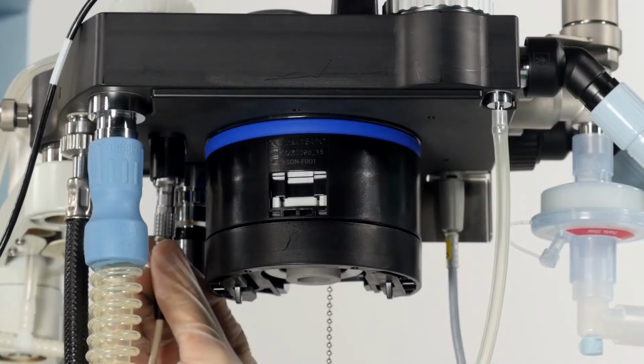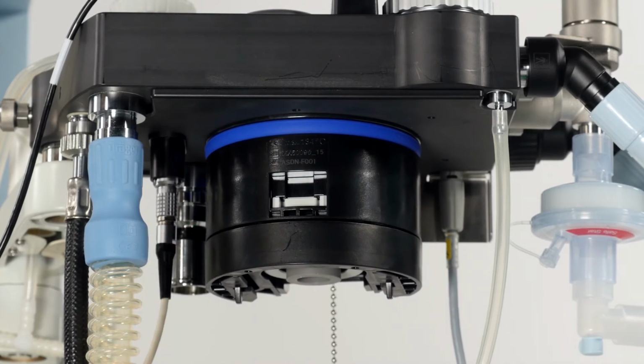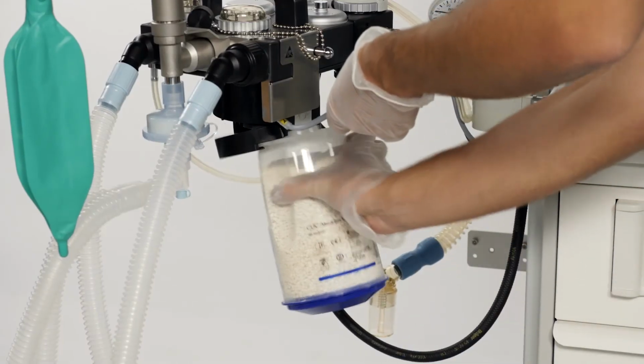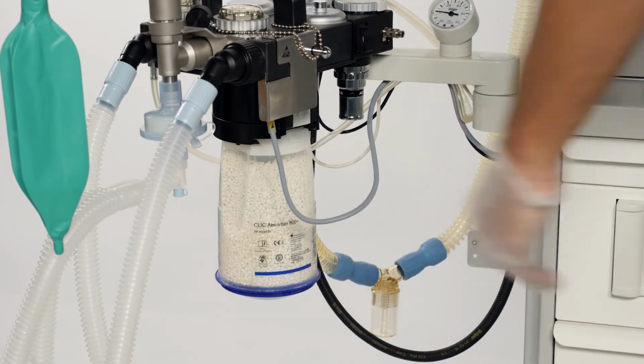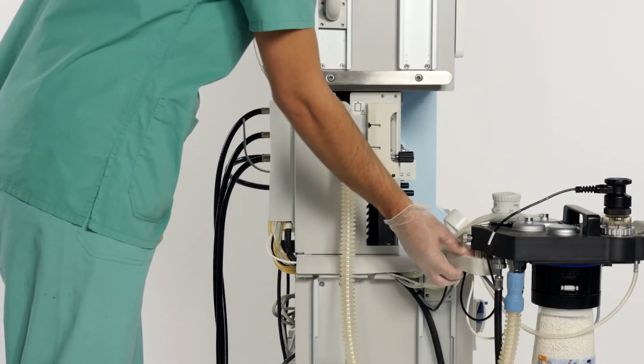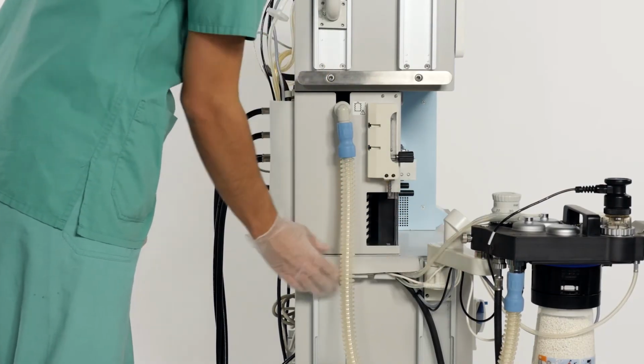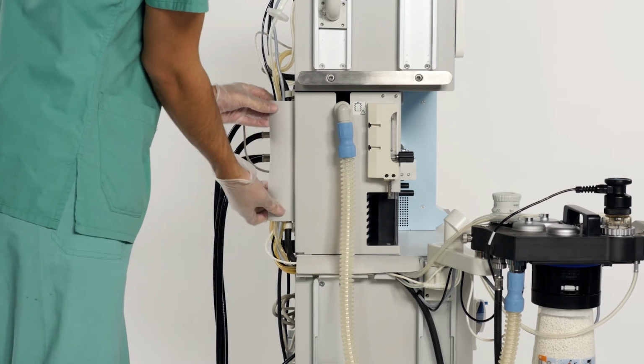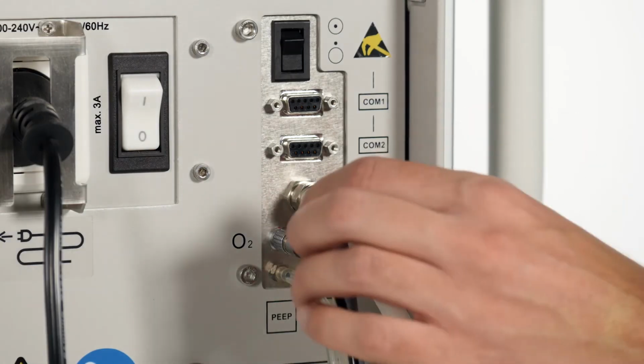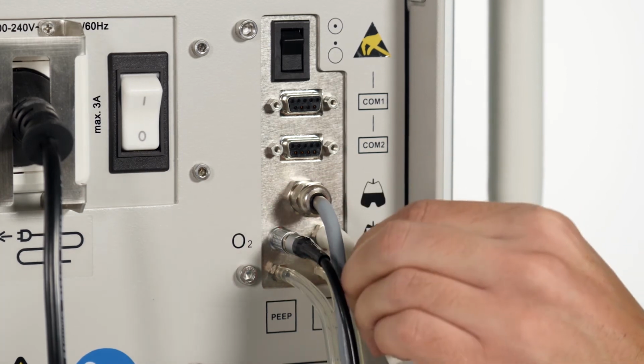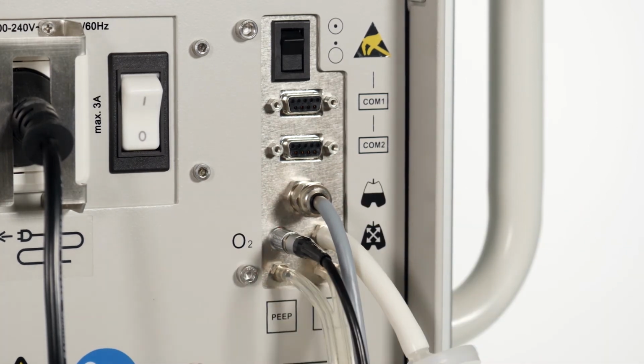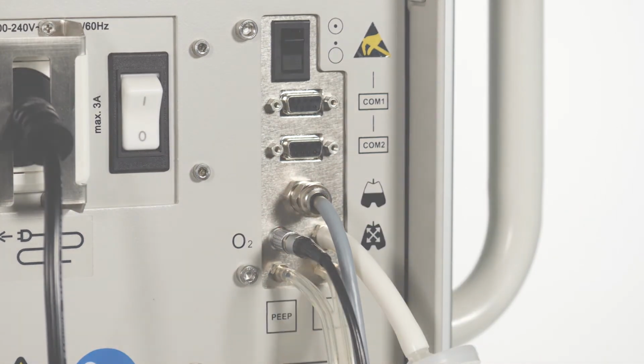Place the cozy heater connection on the port on the underside of the breathing system. Install the soda lime canister. Fit the cables into the cable channels at the side and rear panel of the Fabius. Make sure that all measuring lines and sensors are securely fitted on their corresponding ports on the connector panel.